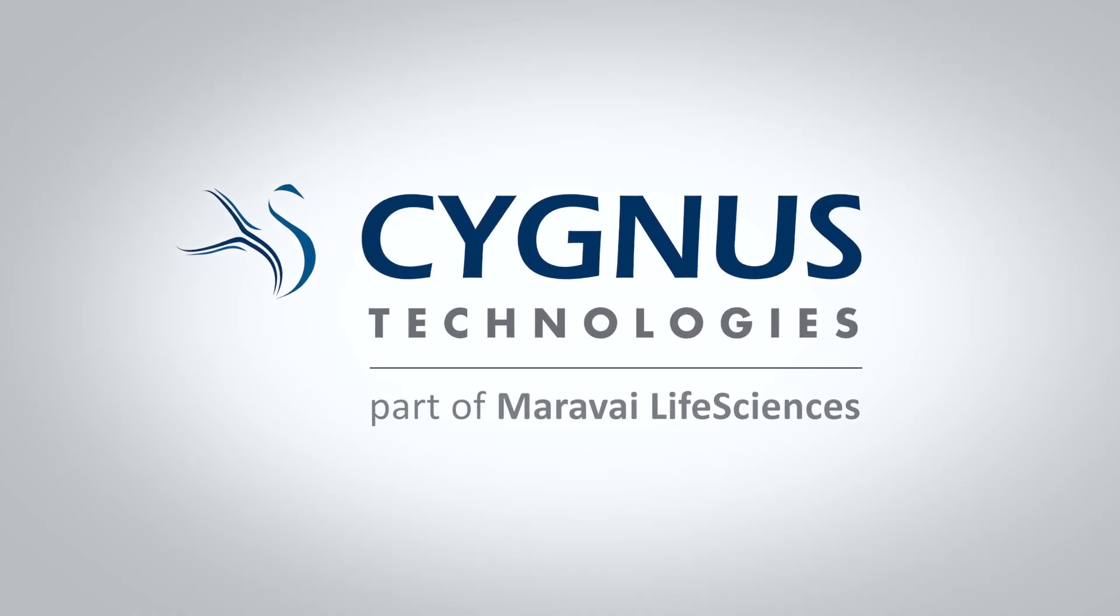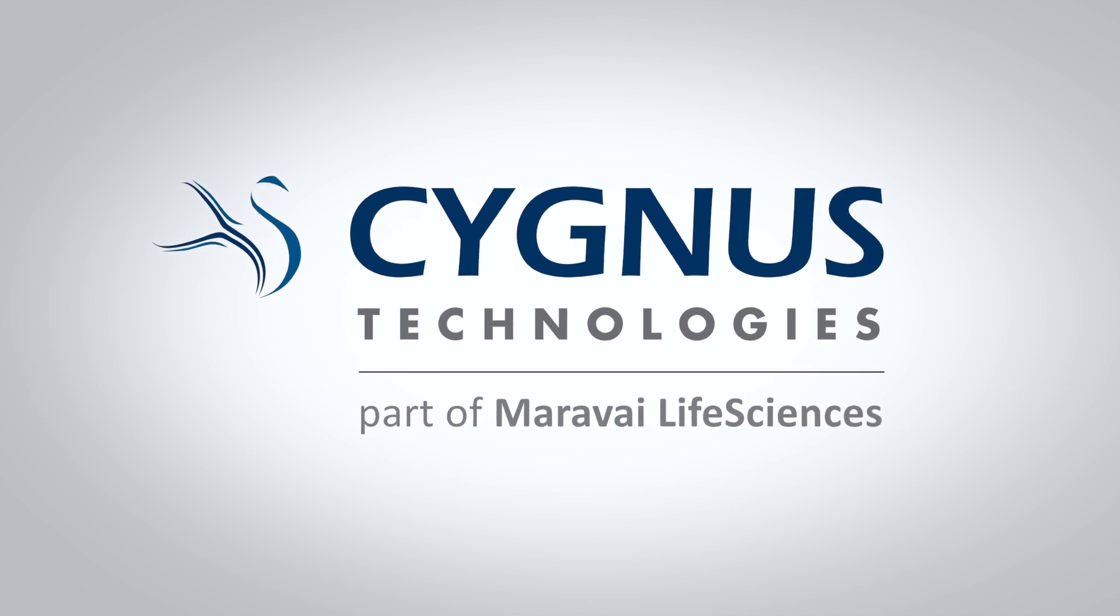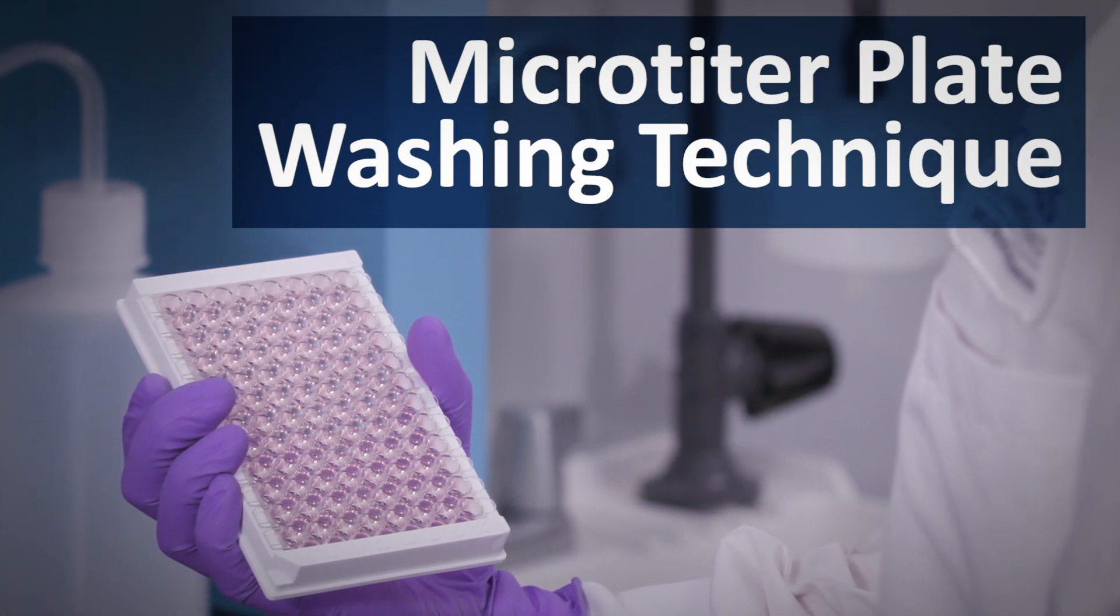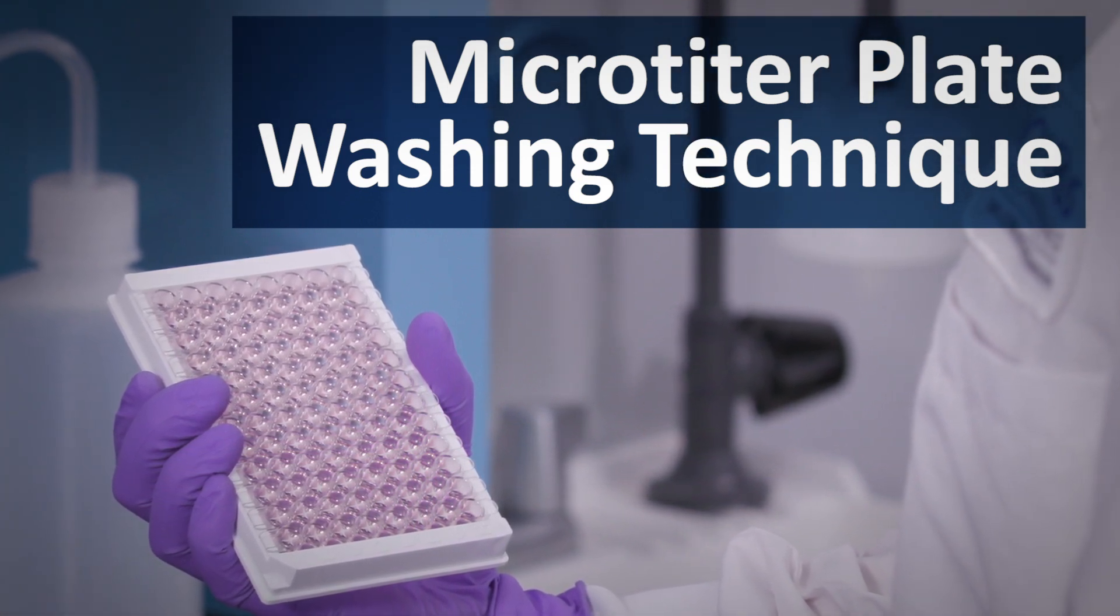Washing of the microtiter plate is critical to the performance of the ELISA. At Cygnus Technologies, we've experienced that most common customer problems are caused by microtiter plate washing equipment or bad technique.